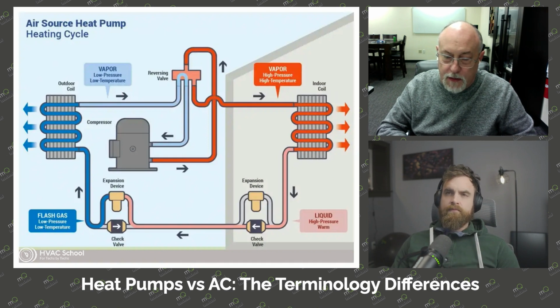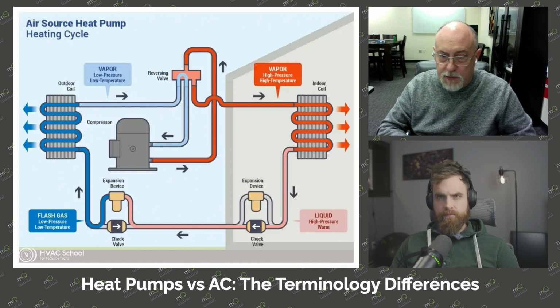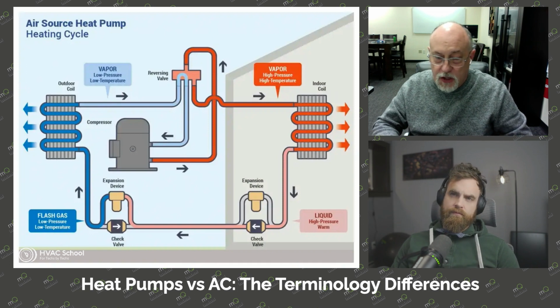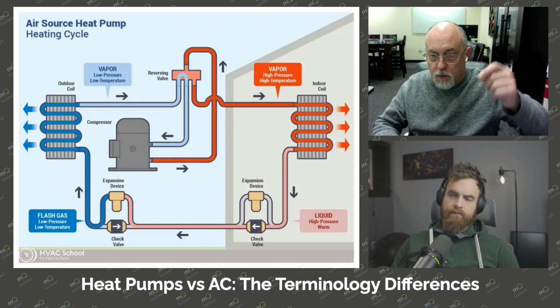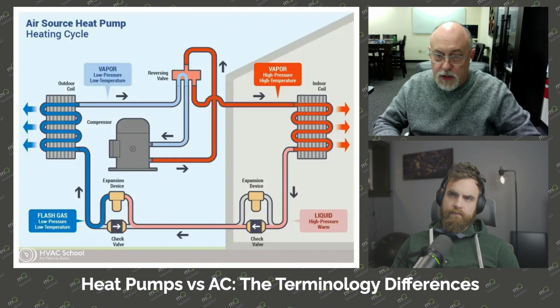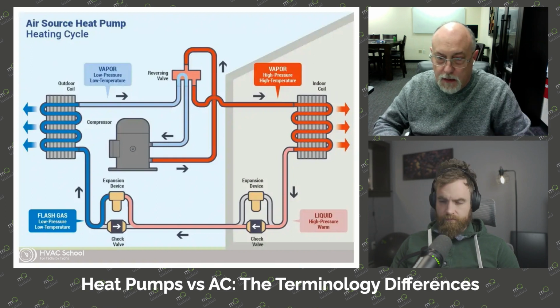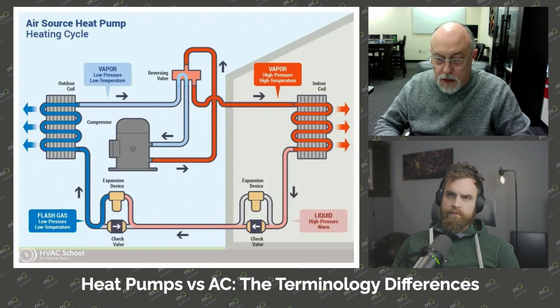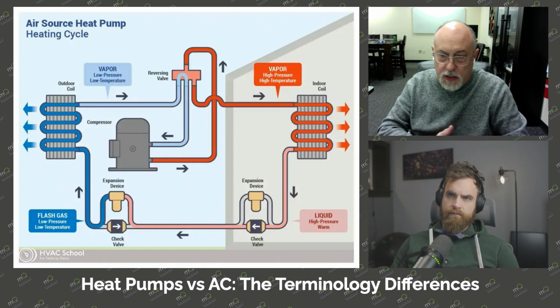So you either have to take a panel off the heat pump, or you have to take the condenser fan loose and reach down inside and put that probe inside the outdoor unit itself. And I usually position that switch in case that unit shuts off, so I can reach in with a little rod or something and press the button on the switch and turn it back on again, so I don't have to take it back out of the unit. So now we've got a suction line, or a true suction. We've got a vapor line, that is the interconnecting line between the indoor and outdoor unit. We still have a liquid line.